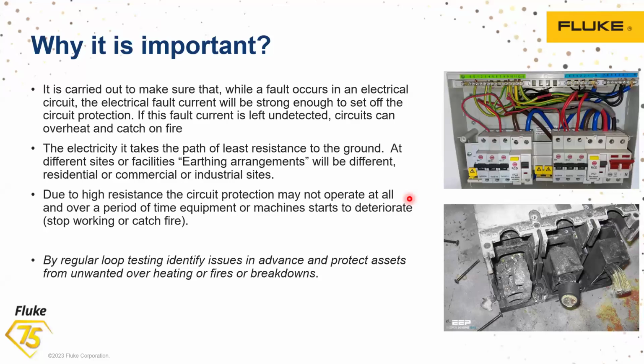It may be commercial buildings, big offices, residential buildings, or industries, everywhere. This test is carried out to find out that when a fault occurs in an electrical circuit, the electrical fault current will be strong enough to set off the circuit protection. If the fault is left as it is, then over a period of time the amount of current will sometimes be so high that it makes the equipment temperature shoot up.